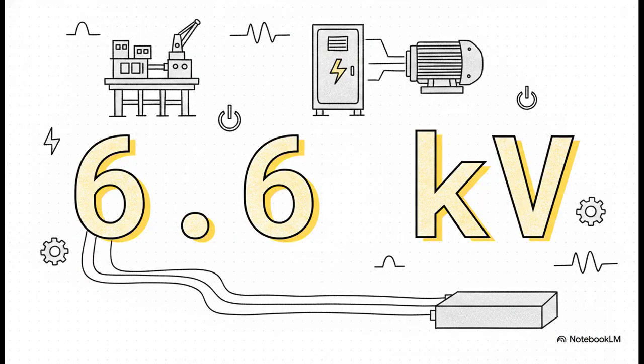That allows you to shrink your incredibly heavy cables in your switchgear down to a size that actually fits inside a cramped offshore electrical module without melting everything down. If you take one number away from this today, memorize this one: 6.6 kilovolts. This is the industry standard and by far the most common offshore voltage for loads above 1 MVA. While extra high voltages are definitely used for those long subsea transmission runs, on the platform itself, 6.6 kilovolts is the absolute sweet spot. It perfectly balances the need to reduce current for space saving against the thick insulation requirements of your switchgear and motor control centers.